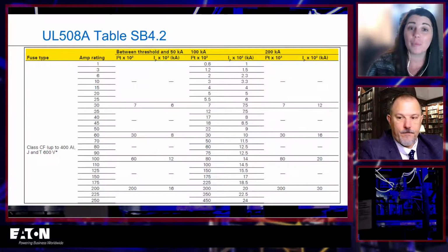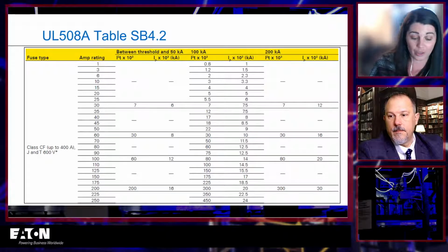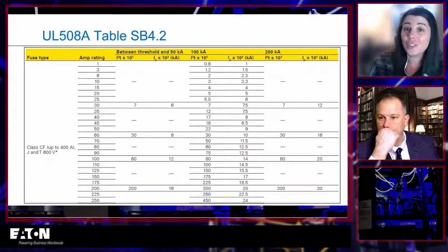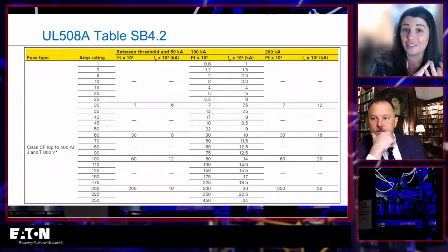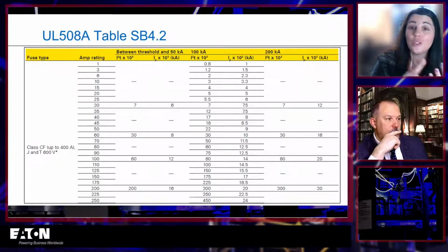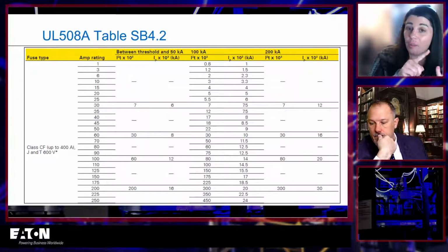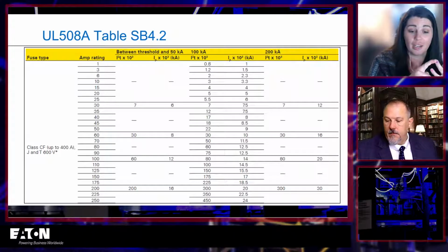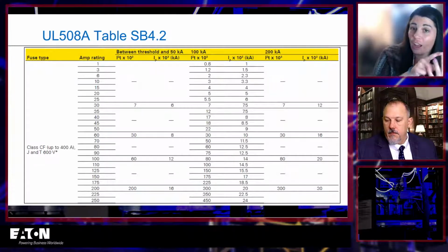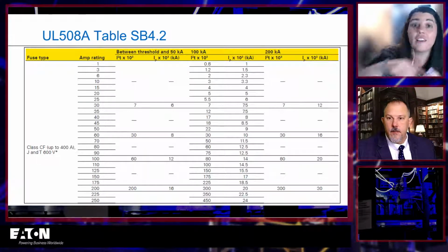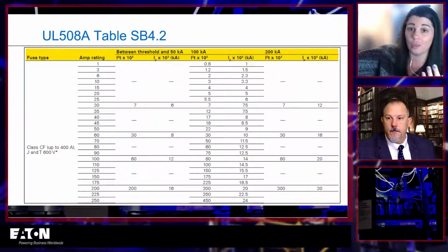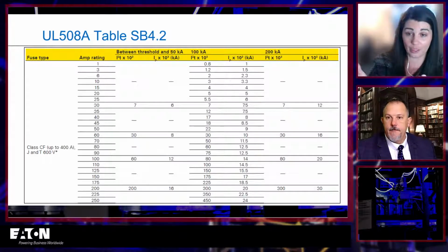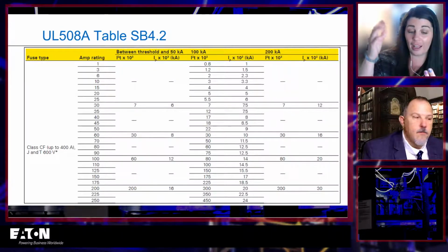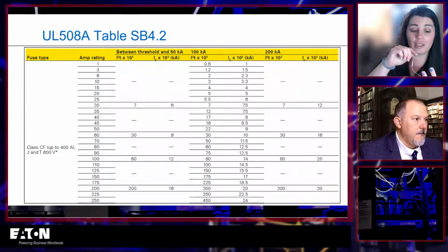Basically, you have to use peak let-through. You can't use it to raise interrupting rating, right? So you can use it to raise SCCR, but you can't use it to raise interrupting rating. And the SCCR of a piece of equipment can never be higher than the lowest interrupting rating in the power circuit, even if you have an upstream fuse that has a lower peak let-through. So it depends.